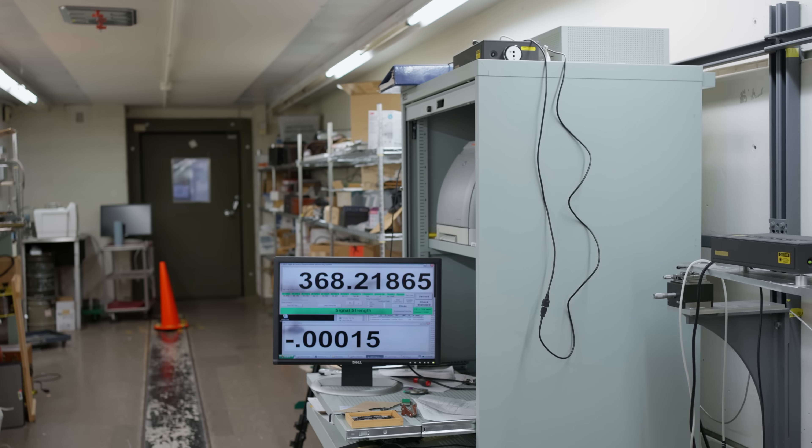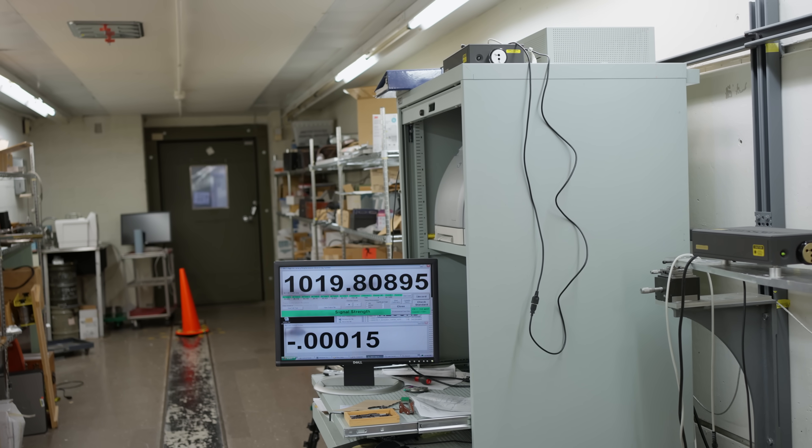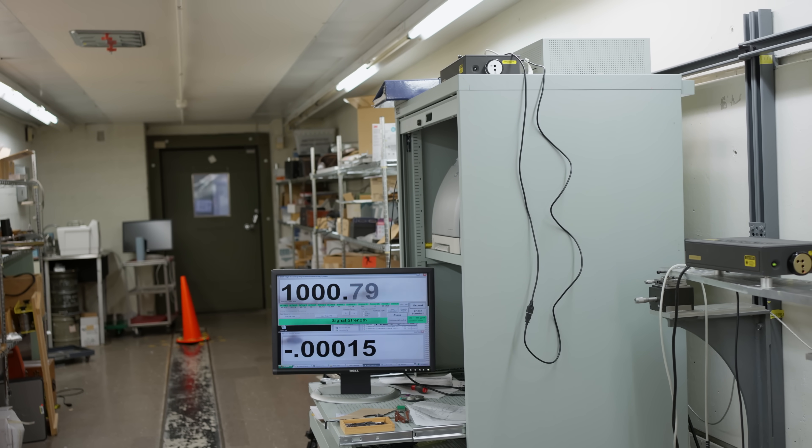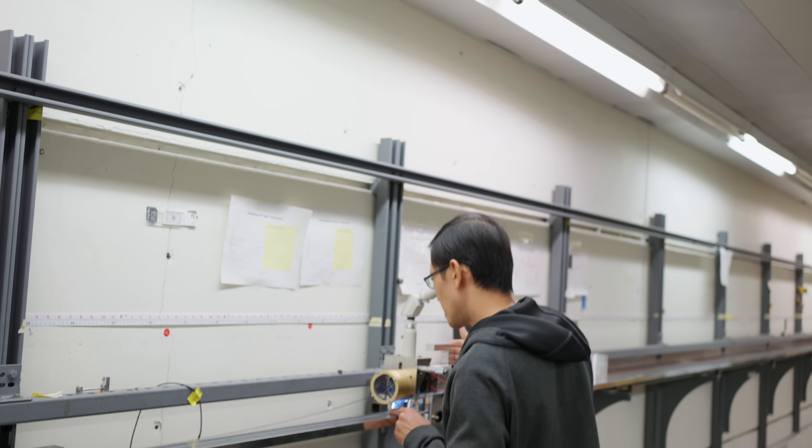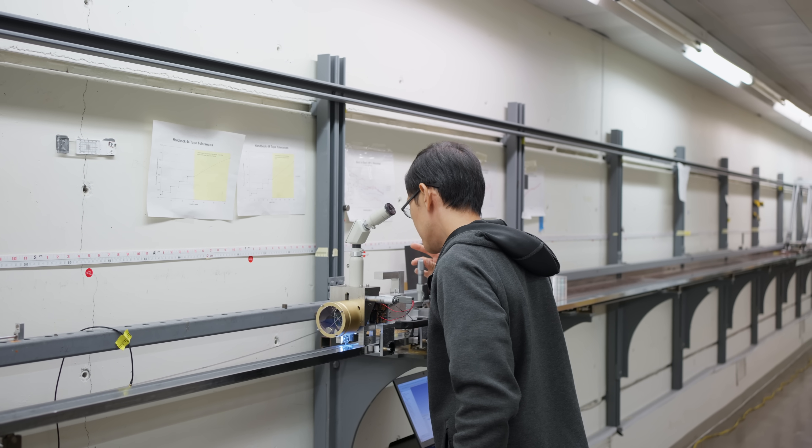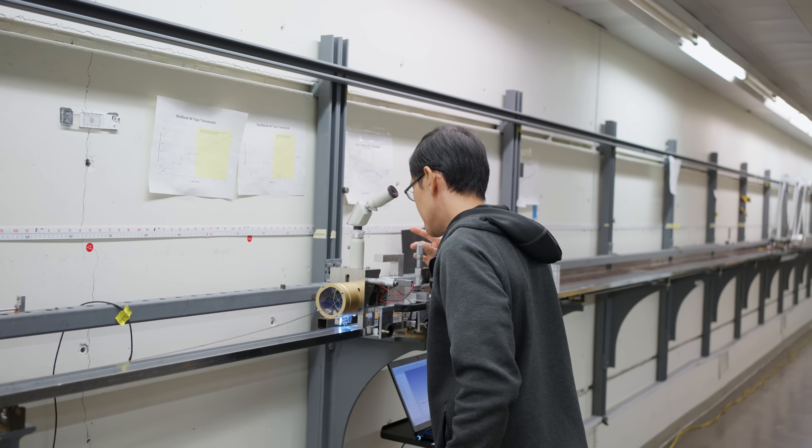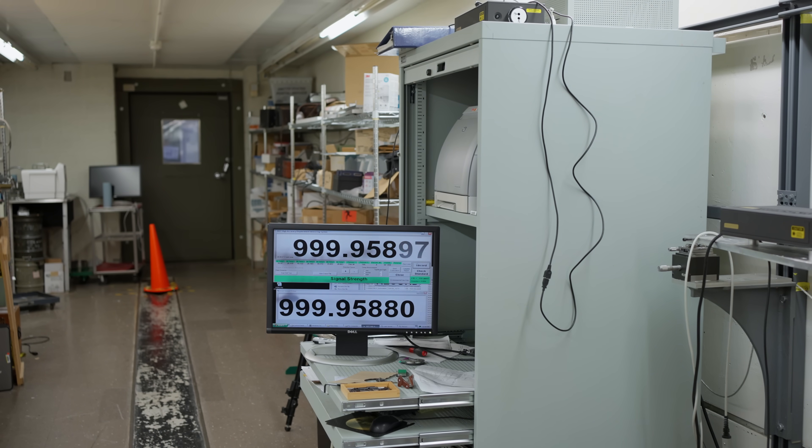That it's been zeroed, we can move, and you can see that it is tracking my displacement from the zero mark. And when I get close to the one-meter location, I will look through a microscope, align the crosshairs to the one-meter mark, level the carriage. Good to go. And that is the distance from the zero mark to the one-meter mark.